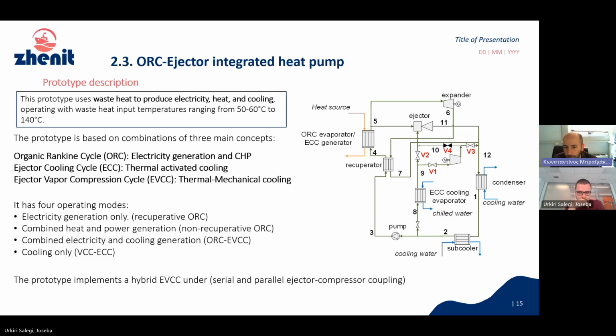And at the same time, we have the option to use these compressors that you see on this layout. And I will come back to this point later. And in this case, as I said, we have electricity produced from the expander and cooling at the same time. And finally, we have a cooling only mode. In this case, we can use either the ejector vapor compression cooling cycle, the EVCC, or the ECC, or the standard vapor compression chiller mode.